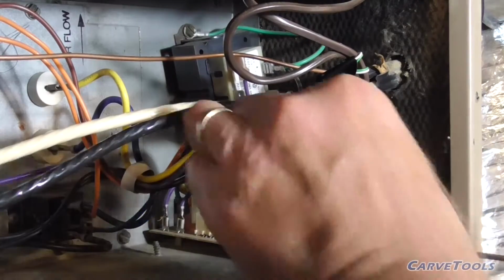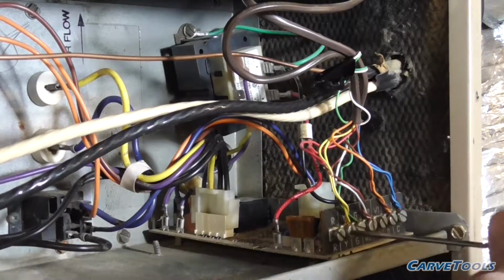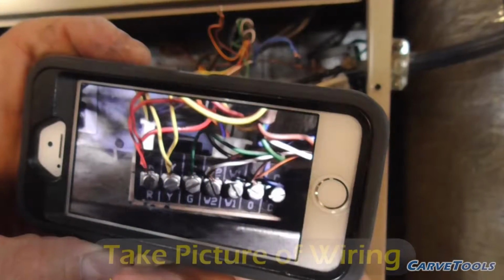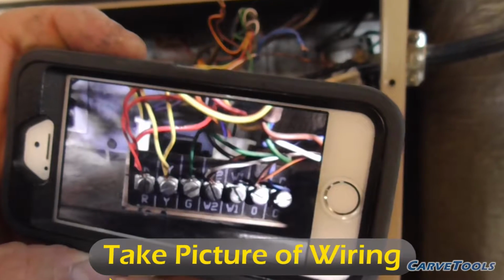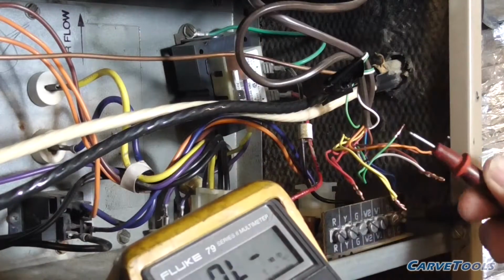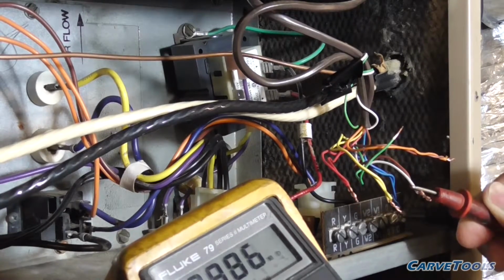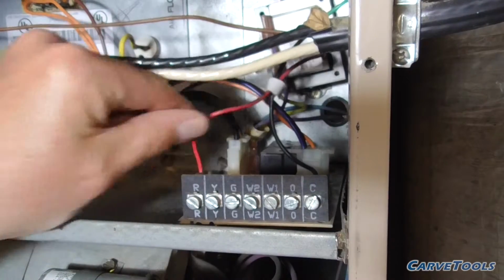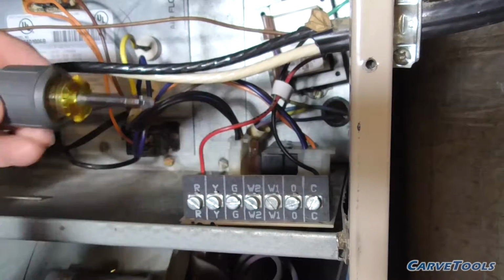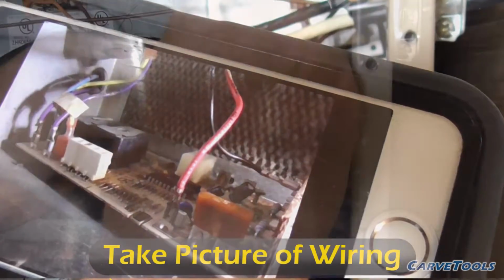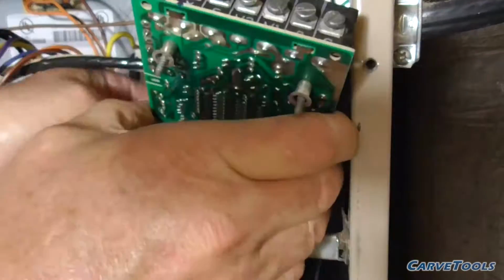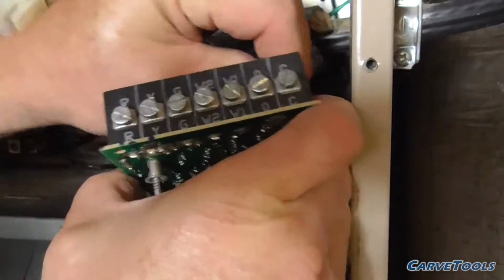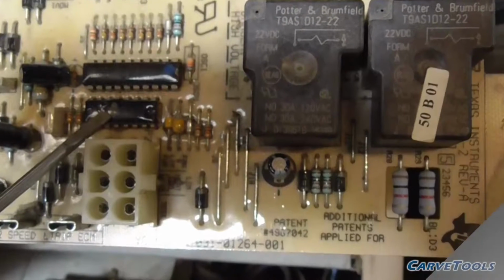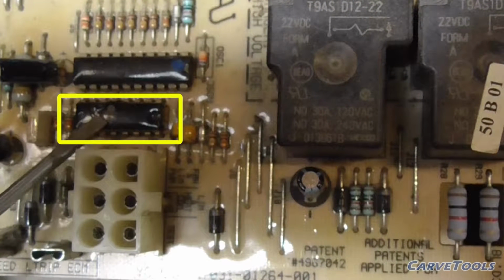Disconnect the circuit breaker again, and I will remove the control wires, but I suspect that the control board is the actual problem. It's always a good idea to take a picture so you'll know where each wire is connected. I don't measure any shorts in the wiring, but when lightning strikes nearby, the energy can just go anywhere. It will search out random electrical and electronic devices, and you just never know. I remove the fan and heat control board so that way I can take a better look at it. Here's the removed control board, and I see there's an IC chip that may be damaged, and I suspect that this is probably where our short is caused.